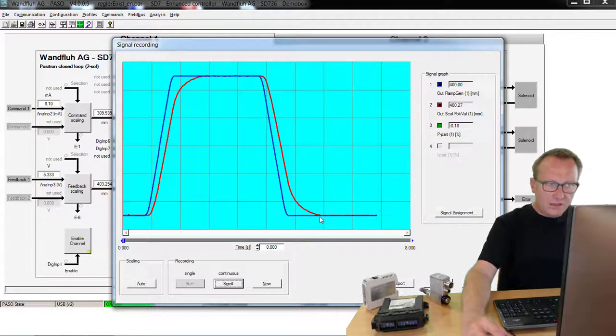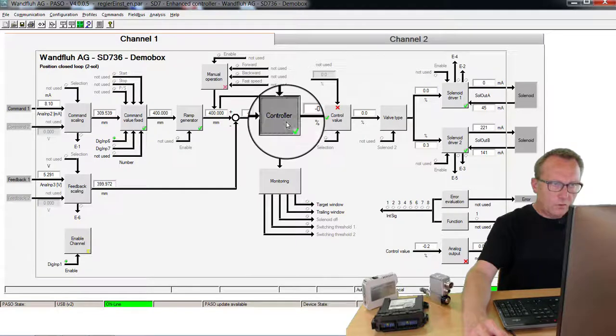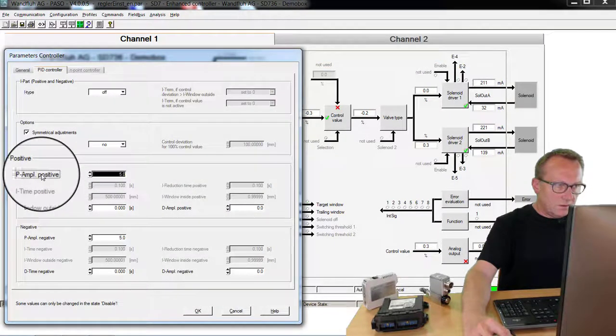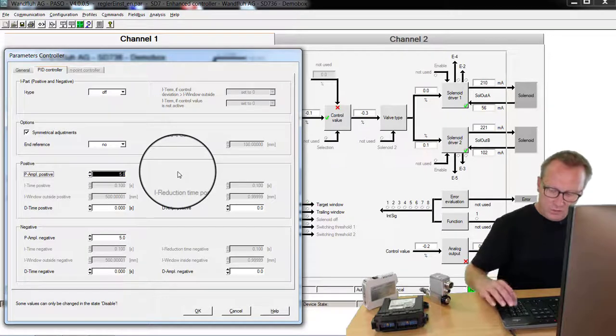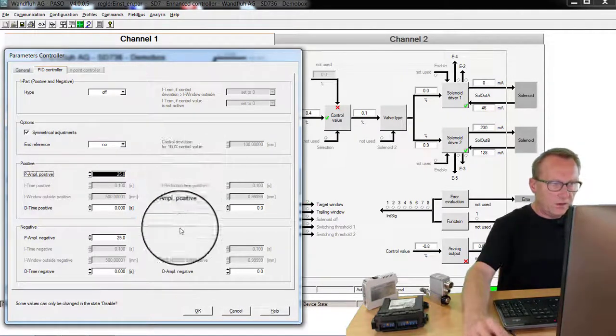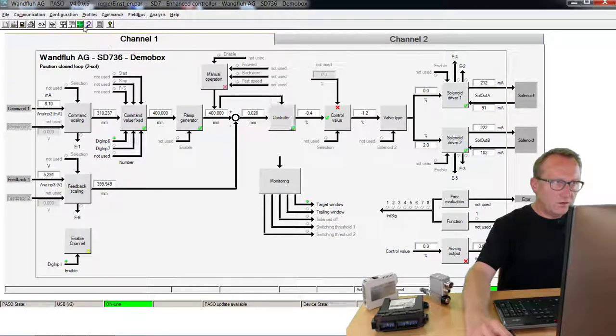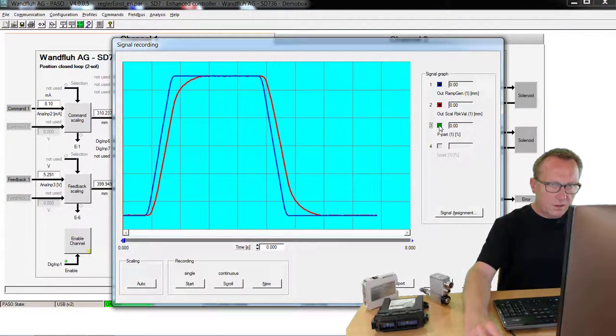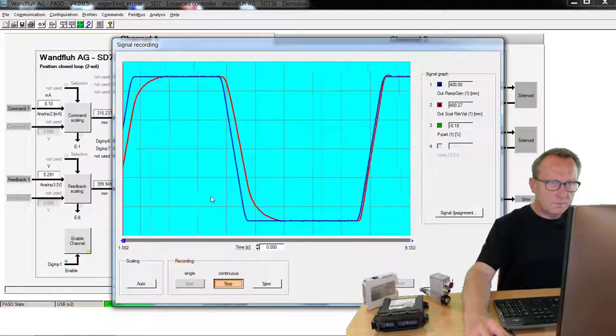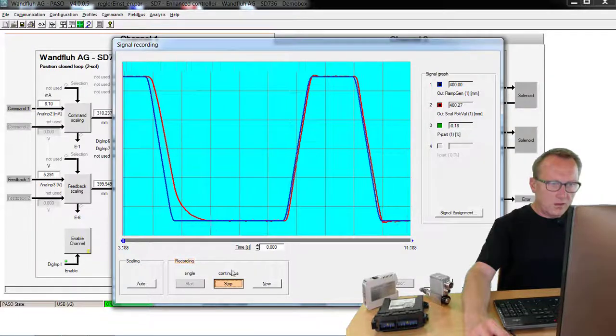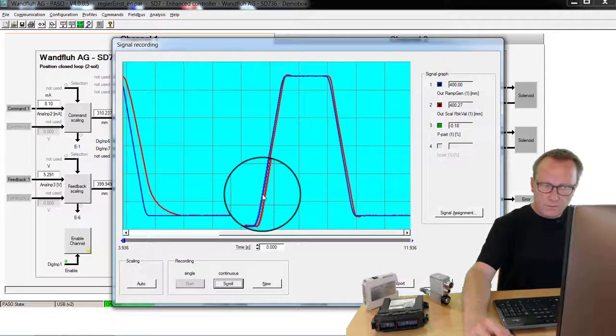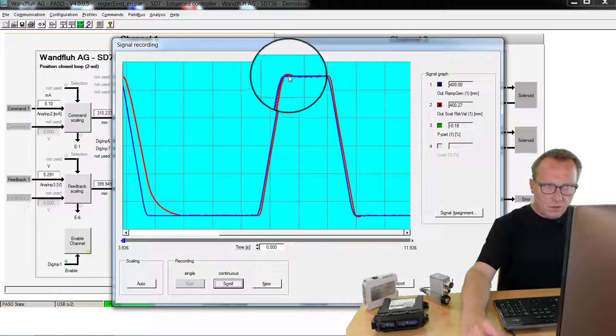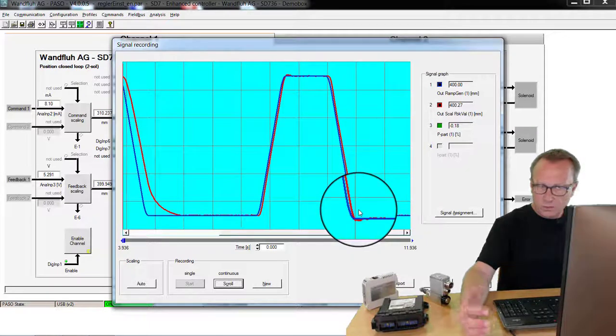We can try to optimize this. We go back to the controller. And I increase now the value of the P amplification. For example 25. We go back to the signal recording. Start again. Now you can see the control deviation is very good. We have optimized the system. But now we have an overshoot for moving into the position.